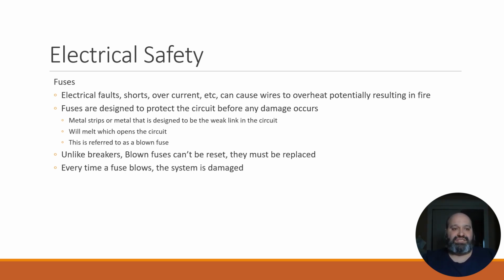Fuses are basically just a metal strip that's designed to be the weak link in the circuit, and it'll melt, opening the circuit like a switch, except that it can't be reclosed. It actually has to be replaced. The thing about a fuse is, if a fuse blows, you have damaged the system. So be leery if you walk into a furnace call or an AC call and you see a pile of blown fuses on top of the furnace. It is the tendency of every new technician to just put a new fuse on and call it fixed. Well, unfortunately, there's a reason that fuse blew.